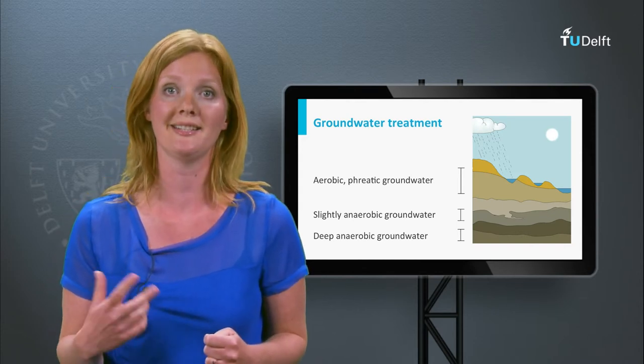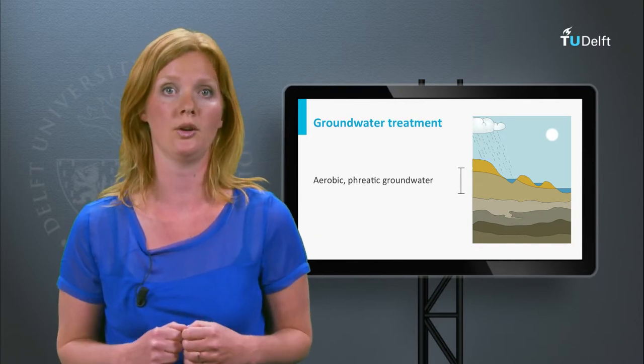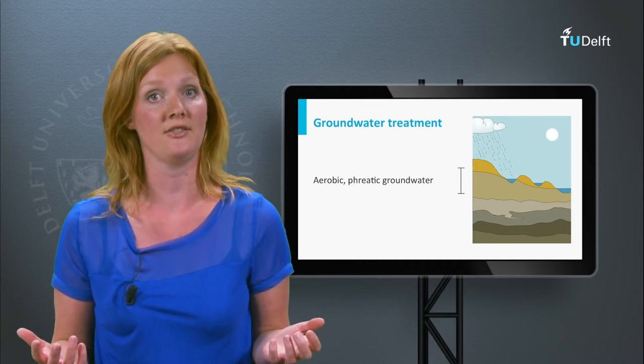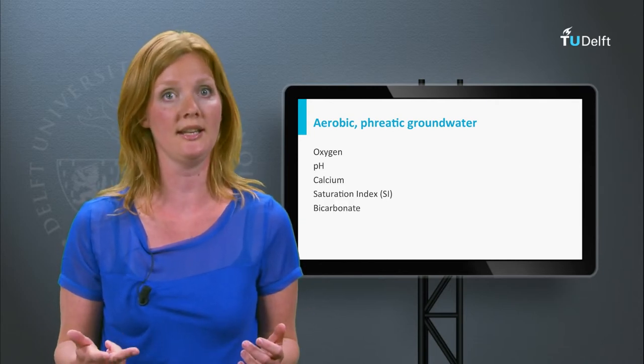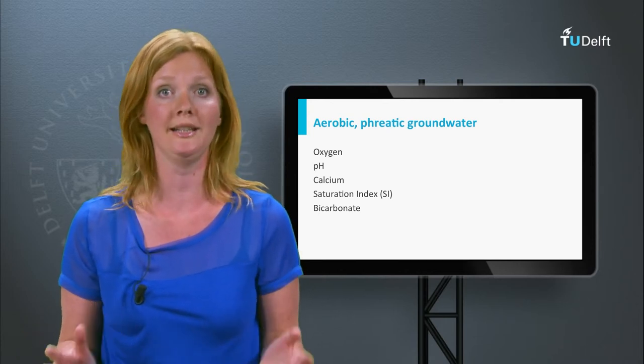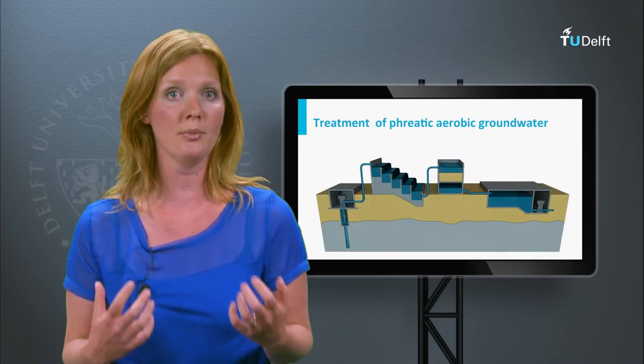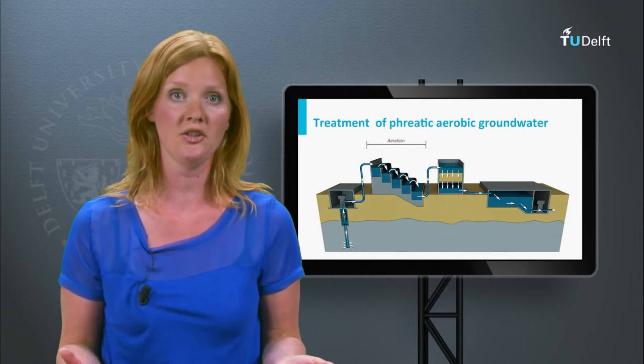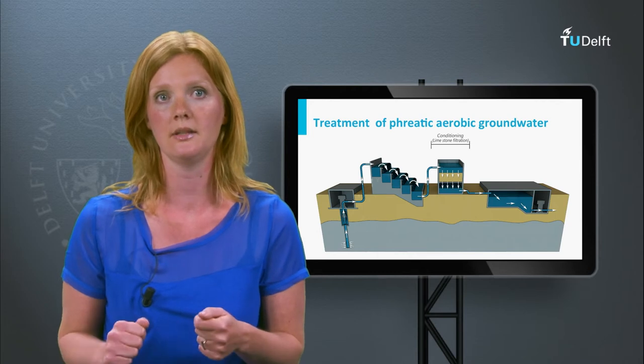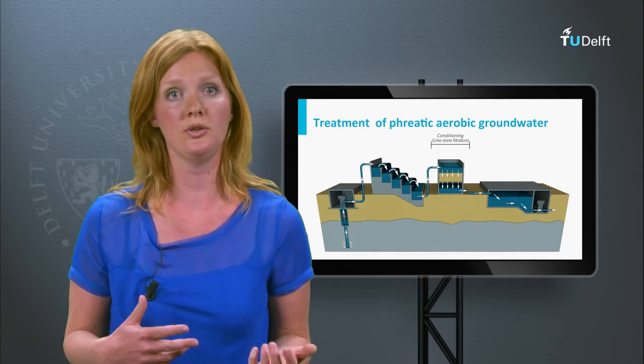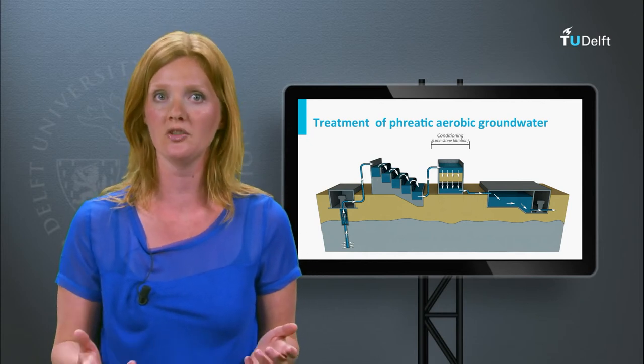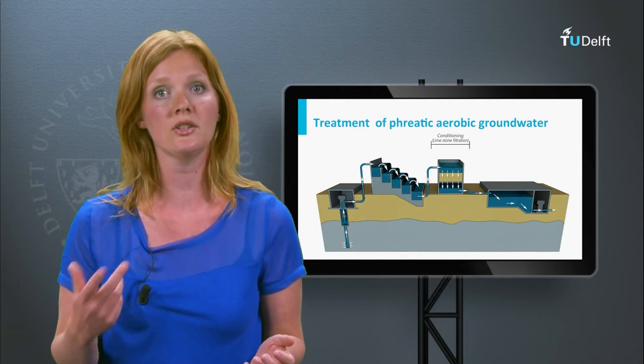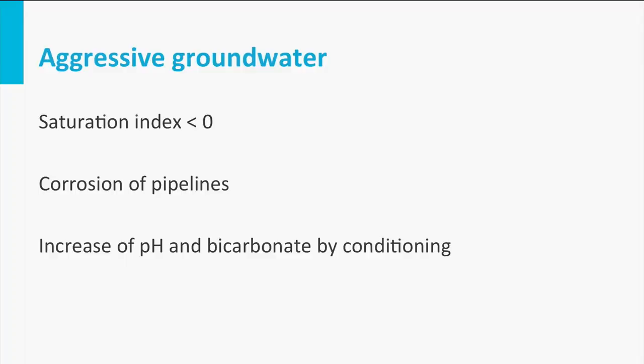Each groundwater type has its own typical treatment scheme. Aerobic groundwater has an open groundwater table, is therefore connected to the atmosphere, and thus contains oxygen. For aerobic groundwater, only the parameters pH, calcium, saturation index, and bicarbonate have to be taken into account — the other parameters generally comply with legal requirements. The treatment scheme for aerobic groundwater is generally very simple and consists of aeration with optional subsequent conditioning or softening. The aeration phase will increase the oxygen concentration and at the same time reduce the carbon dioxide concentration. Conditioning is desired when aerobic groundwater is abstracted from sandy soils where no calcium is available; the water is then called soft or aggressive water.